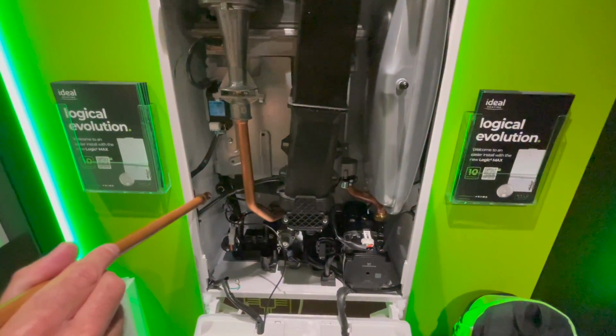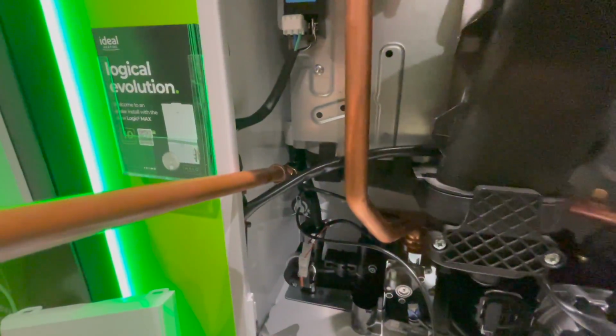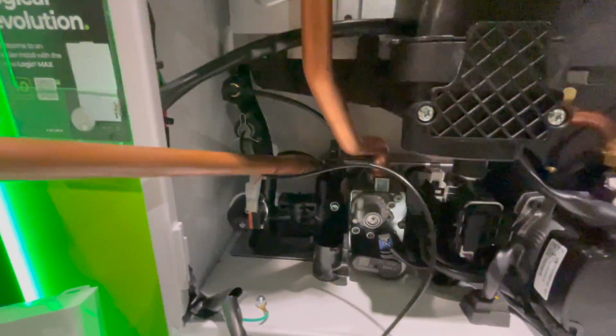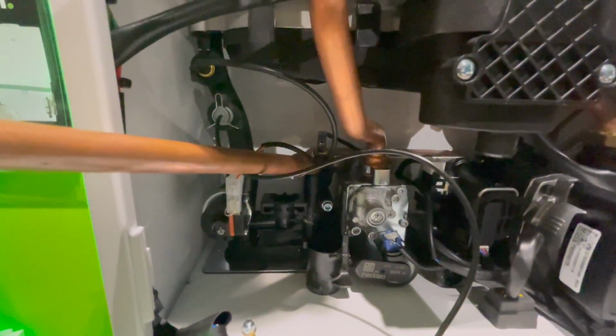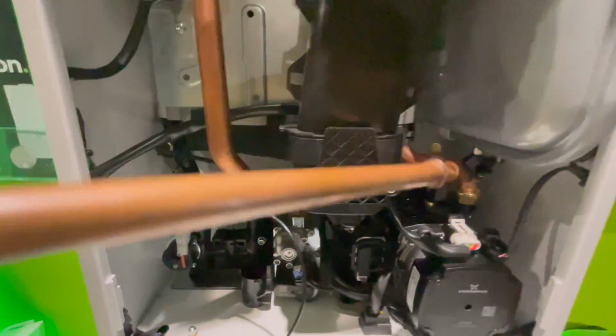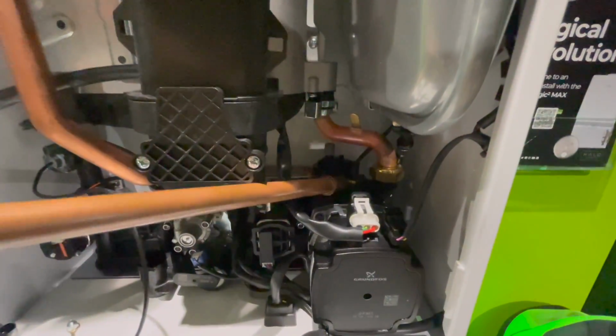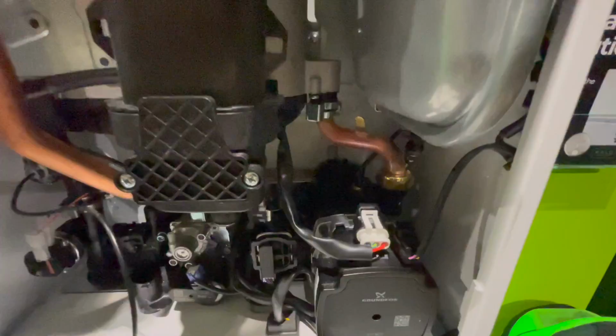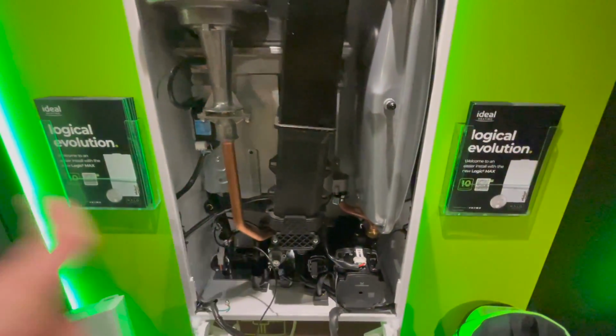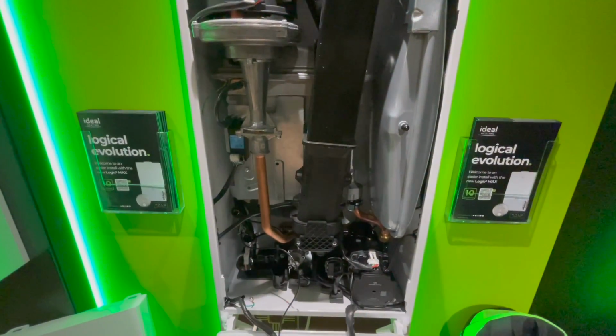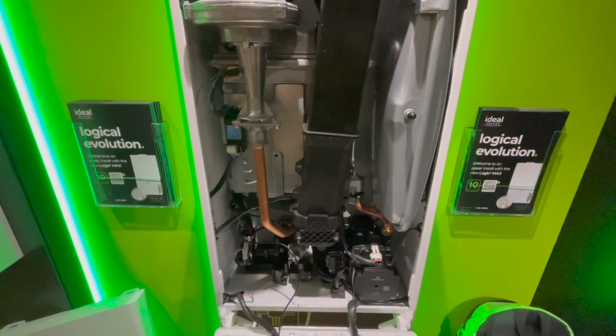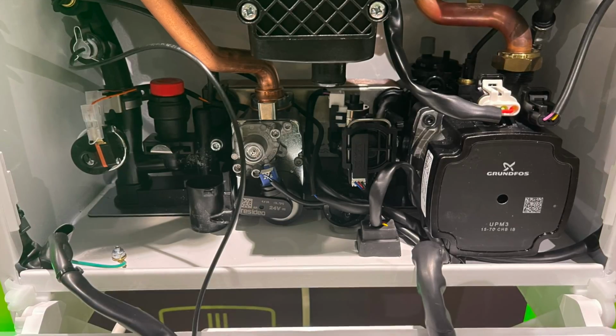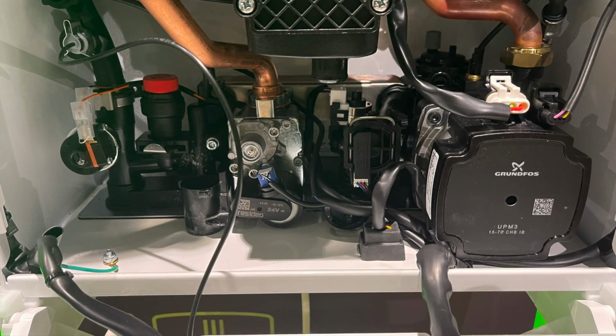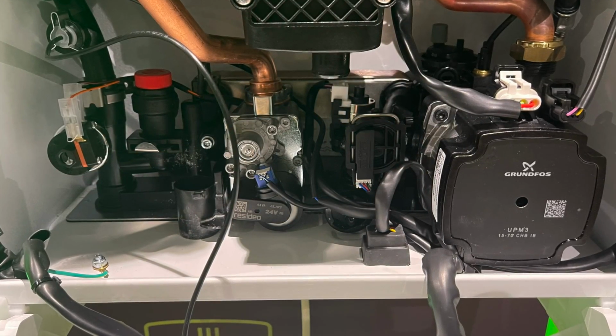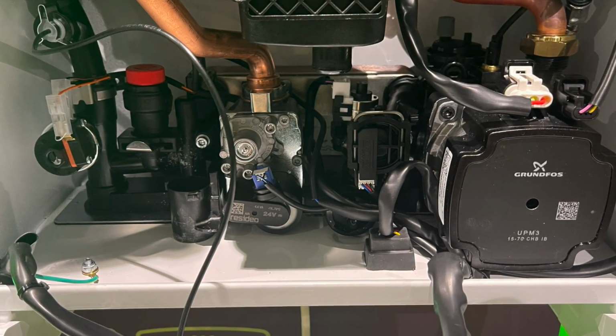But on this boiler now, because of the extra thermistors on the hot water one here, it will now sense the water is preheated, and this is the return one. It will now sense the water is preheated, and it won't spit out hot water because it'll be able to either come on or go off depending on the water going into the boiler. So with these new thermistors now, it makes it compatible with all green heating technologies, including solar therm and hybrid systems.